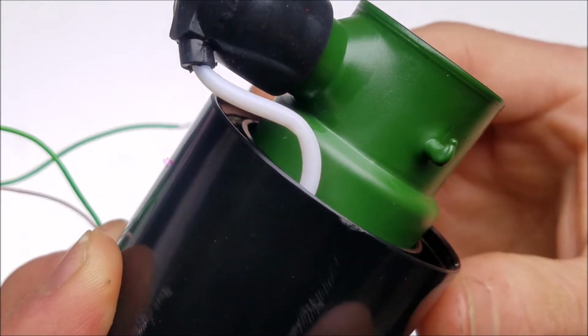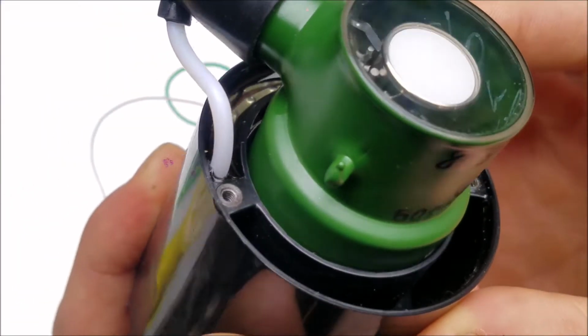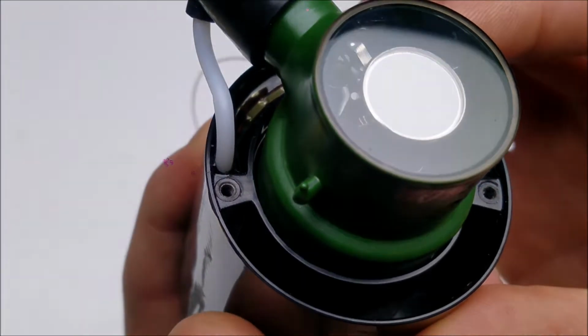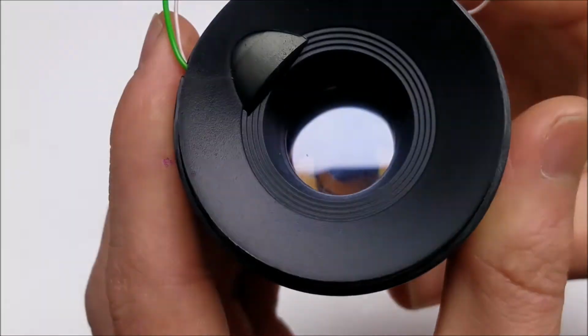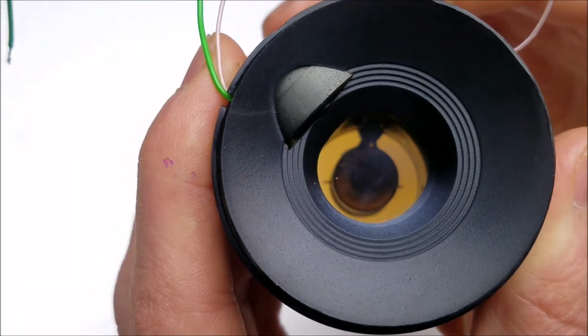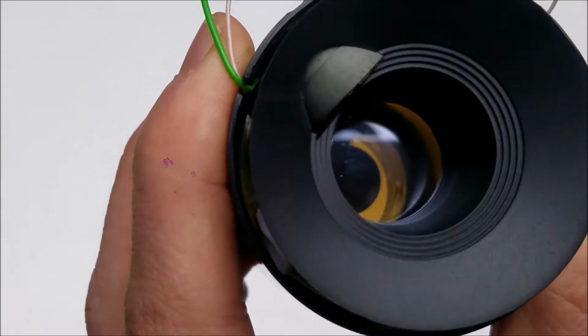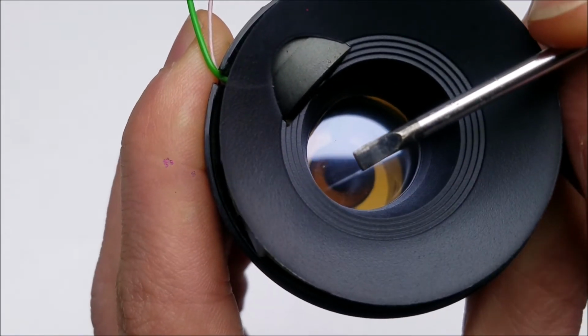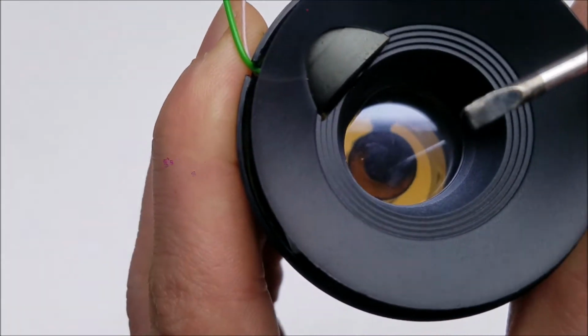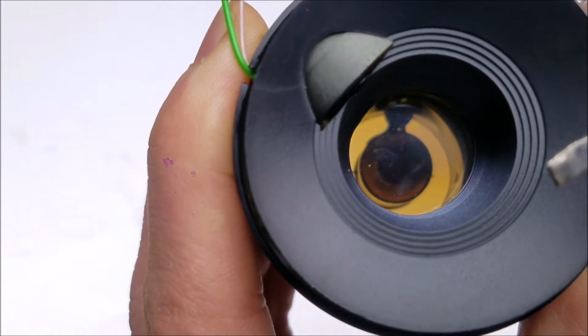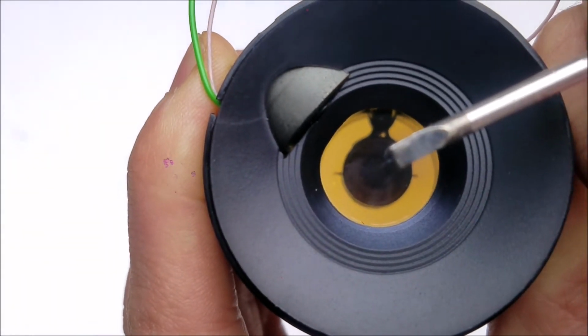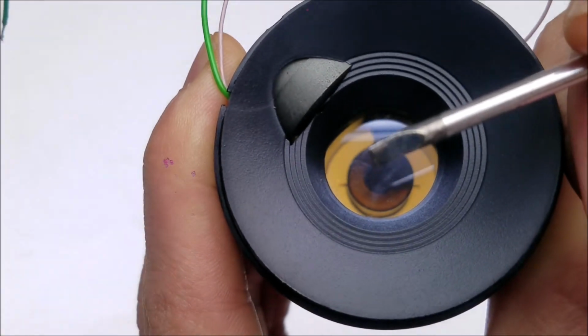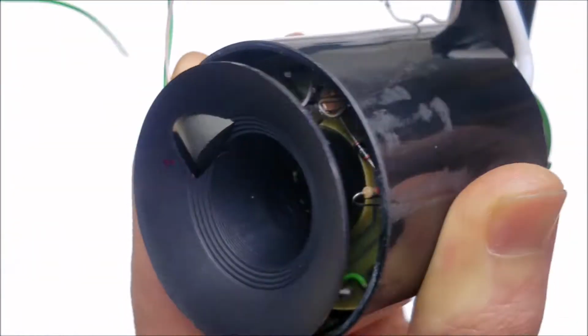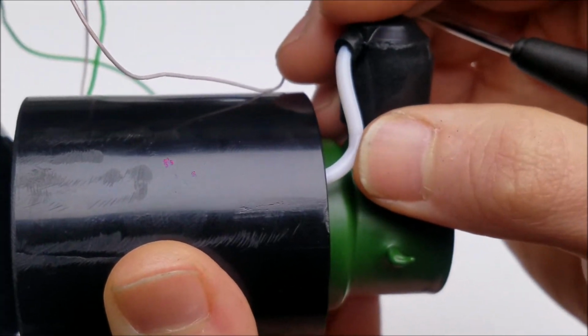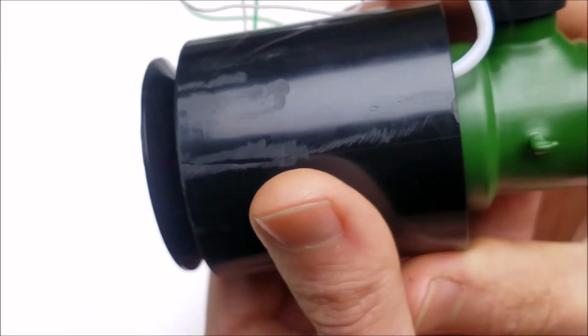We have this white wire that comes off of the multiplier, and that goes up to the accelerating anode on the inside. I can't see it from this end, but we should be able to see it from the other side. Yep. Okay, so you'll notice that right in this center here, there's a little hole. It looks to have a little mesh on it, but that's not too important. But that's where the high voltage goes. So that metal piece right there is charged with a high potential, and that comes from this wire, the multiplier. I think it's like 6,000 volts about.